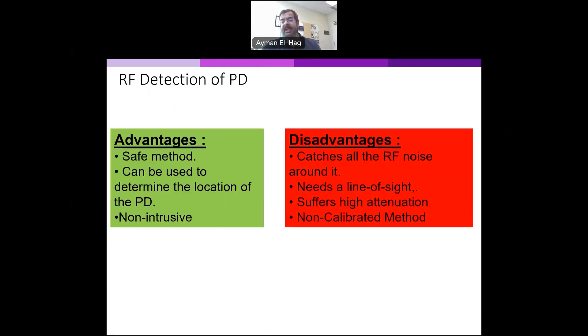Again, there are certain disadvantages and limitations. The RF antenna can catch any sort of noise around us, so this is one of the problems. Then you have to do some denoising techniques. Also, it needs line of sight. Your object that you are detecting, there should be no any sort of barrier between the antenna and that source of partial discharge. Of course, it will suffer from high attenuation, especially if the partial discharge is inside the insulation system.